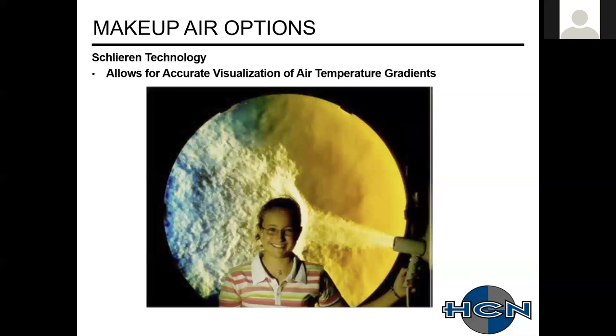And the reason they did this was, if you're coming up to a commercial kitchen hood, if there's no appliances cooking and doing something, you see smoke, but you can't see the heat gradients. So what they did is they have the Schlieren technology. So basically it allows you to accurately visualize those air temperature gradients to make it easier to see that heat.